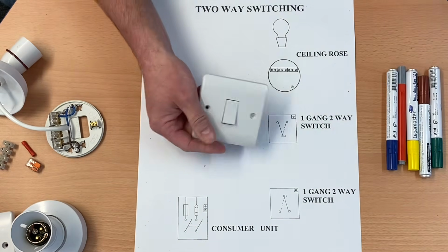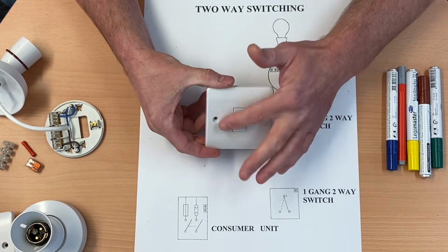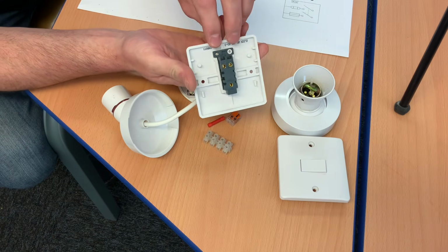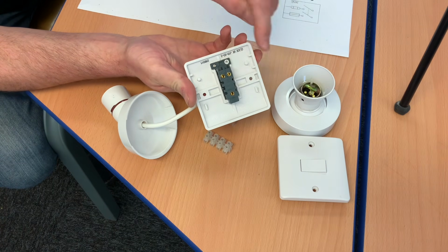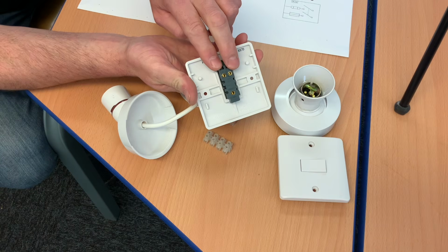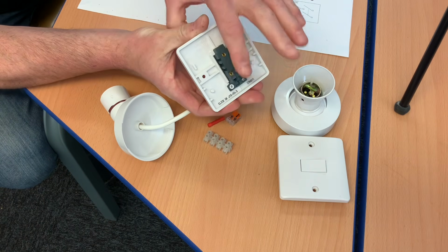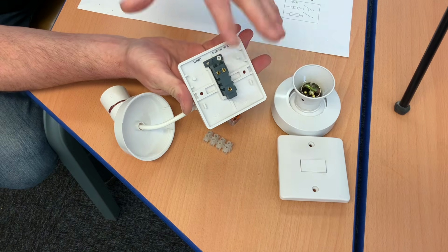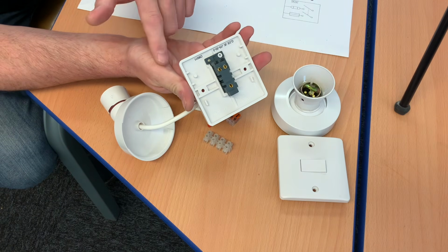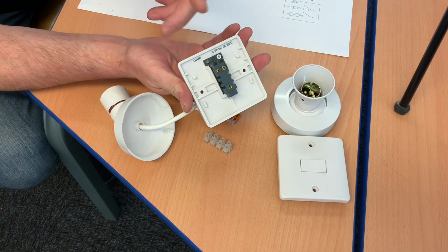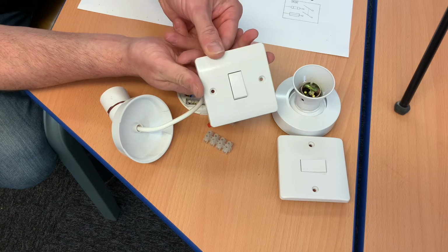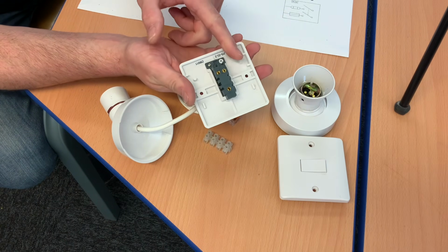So this is a two-way switch, and it's one gang, in other words there's only one switch on it, but as we look here we can see it's two-way. There is a common, an L1 and L2. It doesn't matter, I could have turned it round, there's common, L1 and L2. It's only important that we get the commons correct, and we'll look at that in the drawing. L1 and L2 can flick as they go between them, but students tend to like to keep them in the same place, but you don't have to. So this is a one gang, two-way switch, and we need two of those.